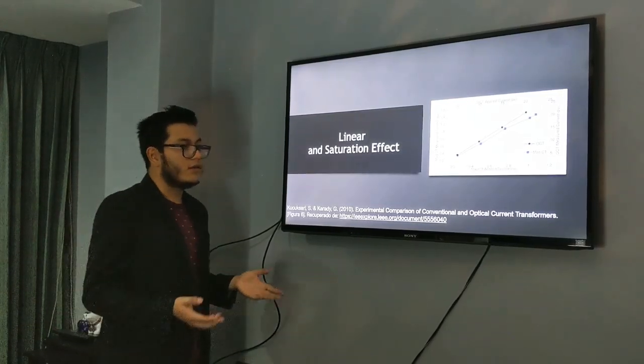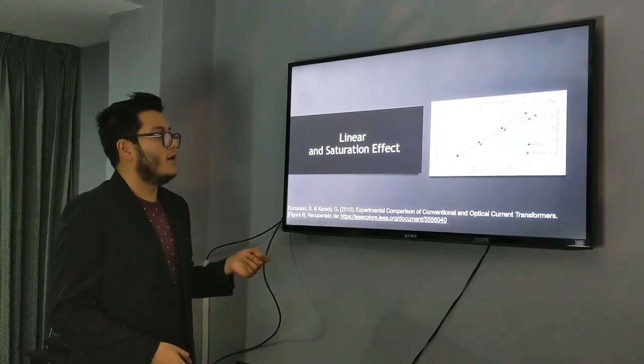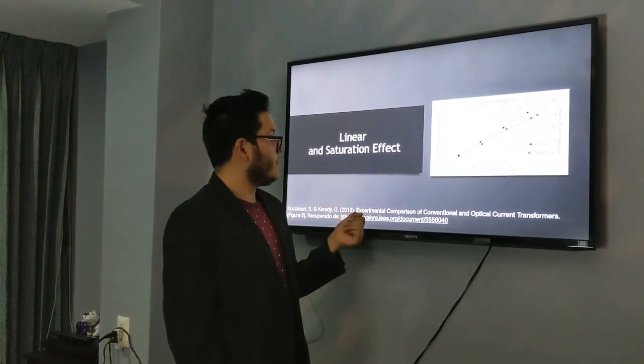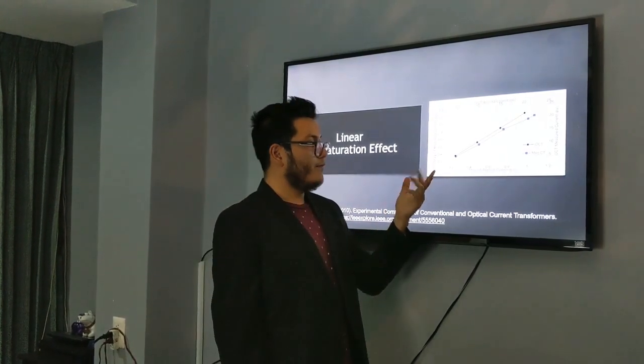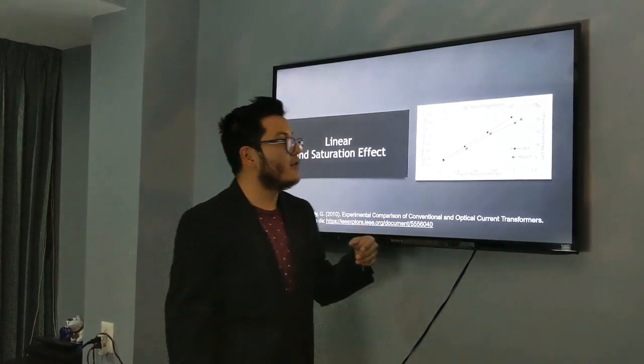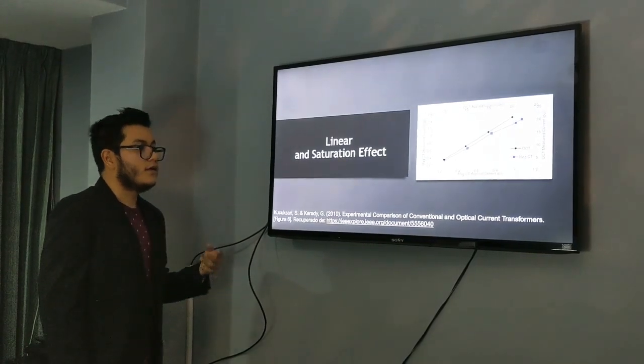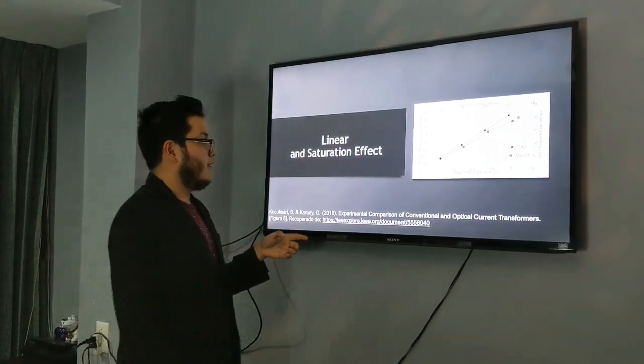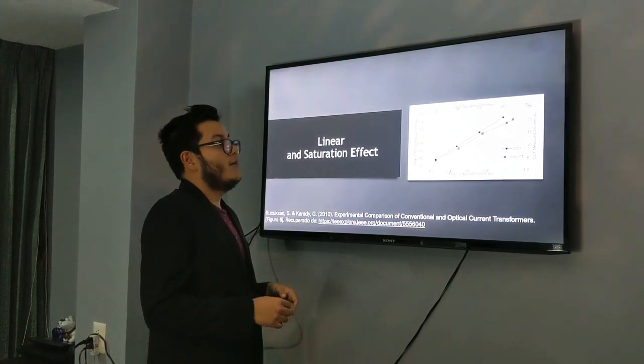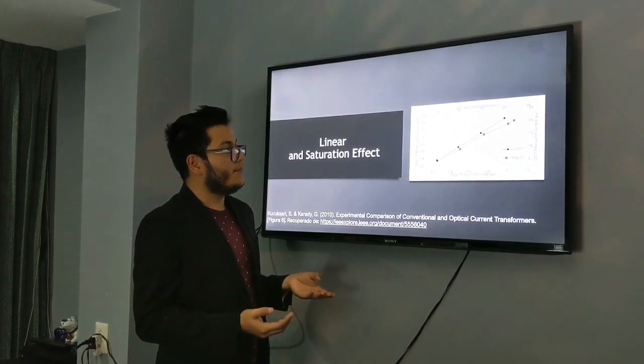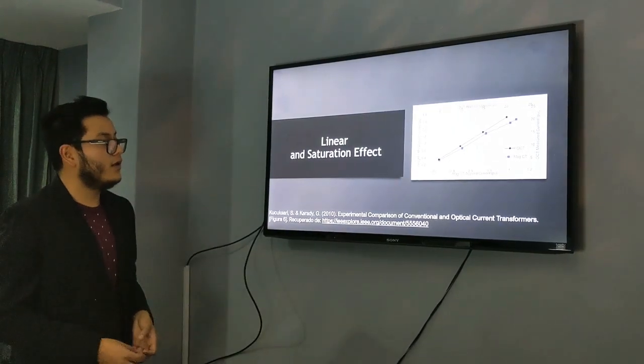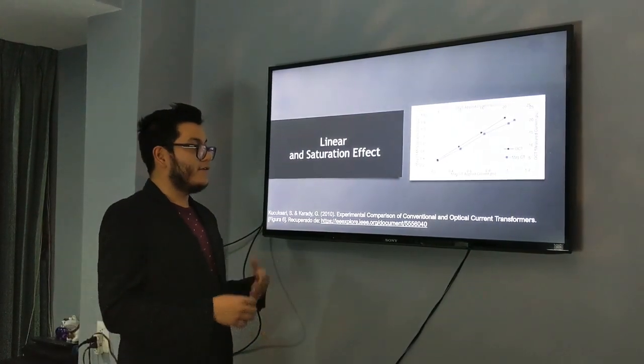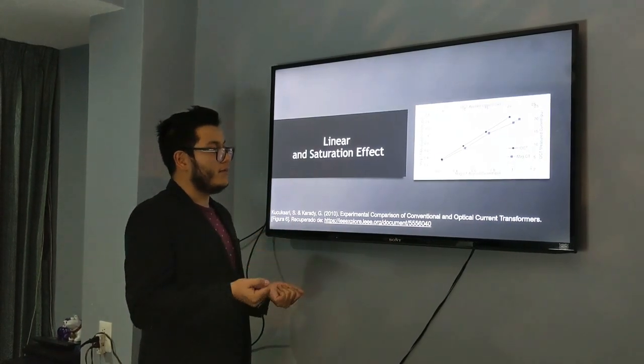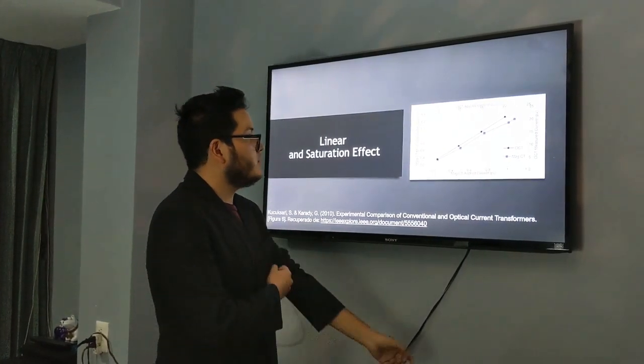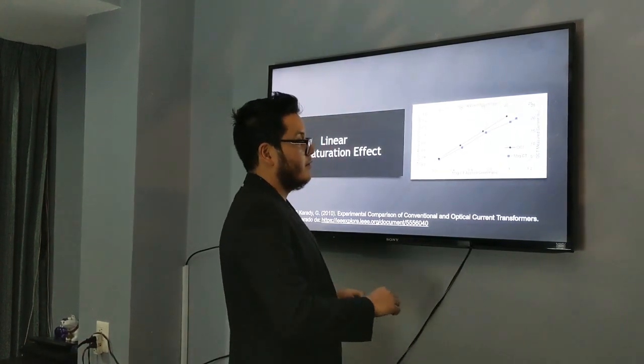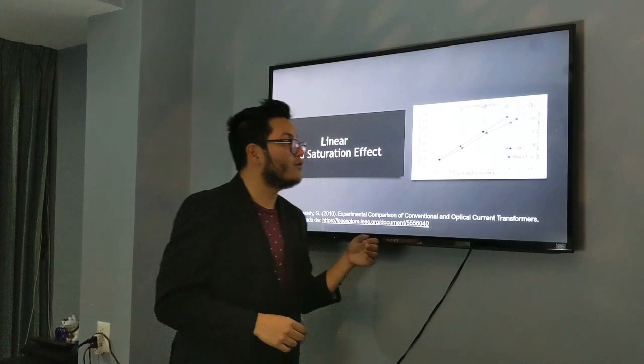The test that was made in this case was linear and saturation effect, and as we can see we have two graphs. The black one being the optical current transformer and the blue one being the magnetic current transformer. The optical current transformer, as we can see, has a very linear behavior, but the magnetic current transformer, after a certain value of current, showed some differences and we started getting some saturation effects.